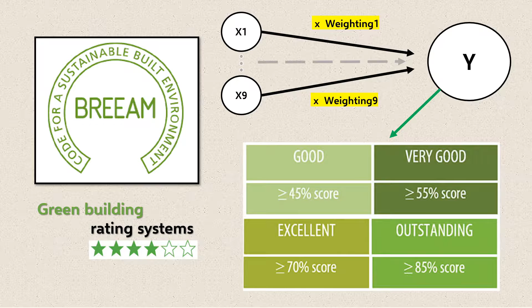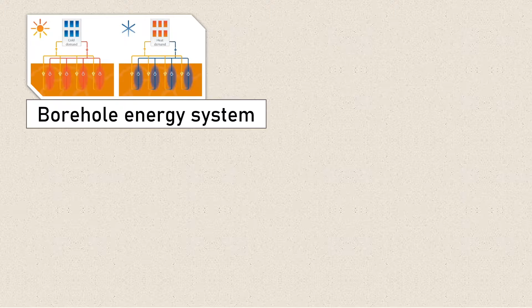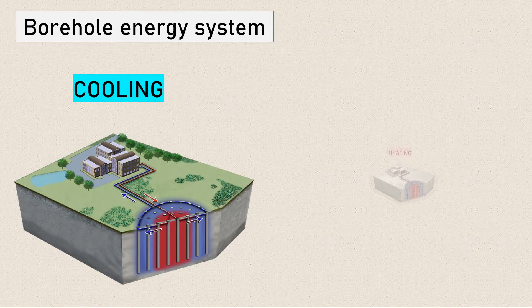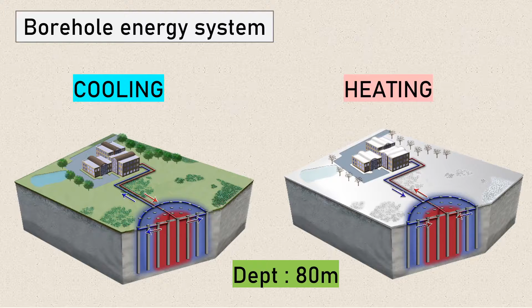Now that we know what BREEAM is, let us see why the Antwerp Porthouse achieved a very good rating. In the BREEAM assessment, a borehole energy system, the chilled beams method, the chilled ceiling method, and optimal light control contributed the most to receiving the very good rating. Now we must understand what a borehole energy system is. In order to provide efficient local cooling and heating, a borehole energy system pumps water to a depth of 80 meters below grade in over 100 locations around the building.